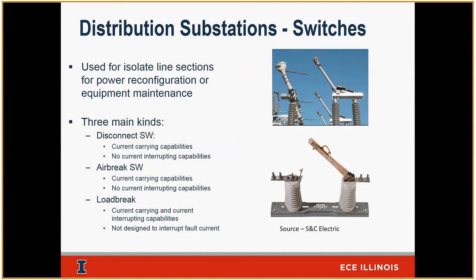So these disconnect switches, like I said, their main purpose is to take equipment out of service for maintenance and also redirect power. These could be operated manually or with a motor. So there are things that are called motor operator switches too. So there's a motor, the recharge coil, you push it and it's on. You can hear it cranking and opening the switch. Or a lineman can come in with a stick, basically place a stick on one end of the switch and just pop it open and it will open the switch. And again, you're basically disconnecting the path of energy to your device.